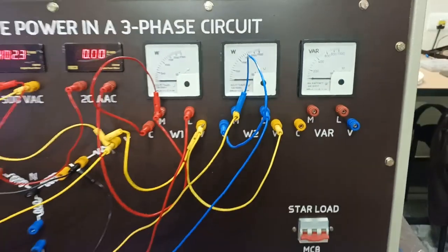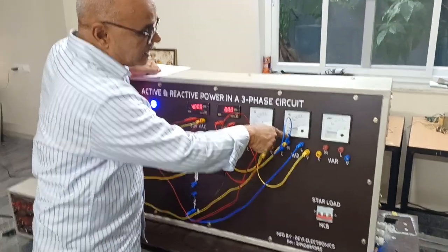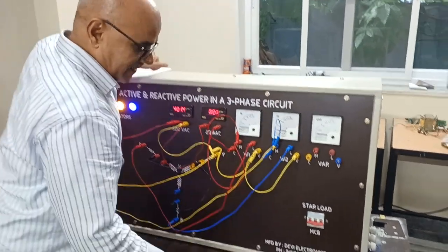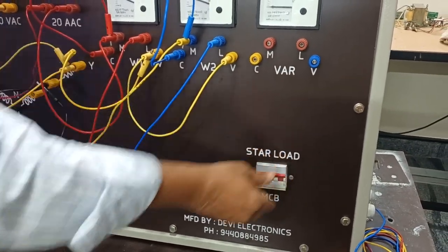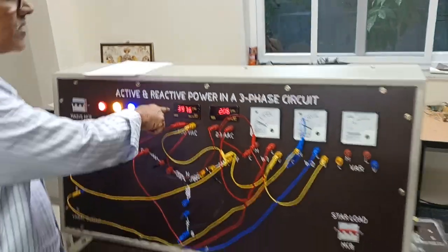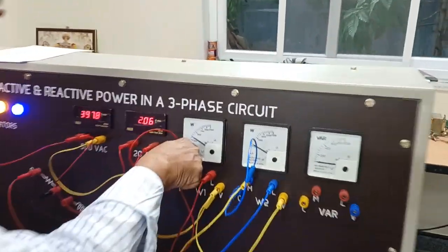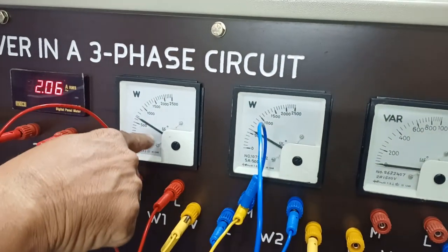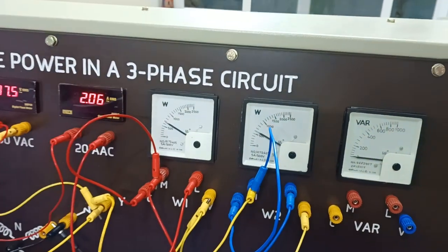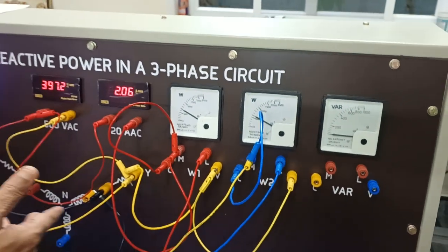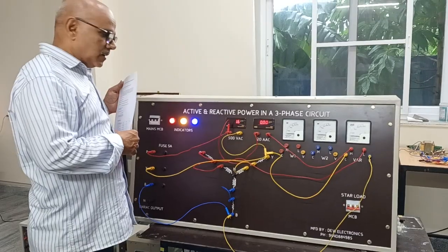In this case I have used two wattmeters, R with respect to Y and B with respect to Y. Now I am going to apply load. At 400 volts, the current is 2.06 amps. W1 is showing around 650 to 700 watts, and W2 is showing 600 watts. If you sum them, you will get the total power. We will do calculations later.